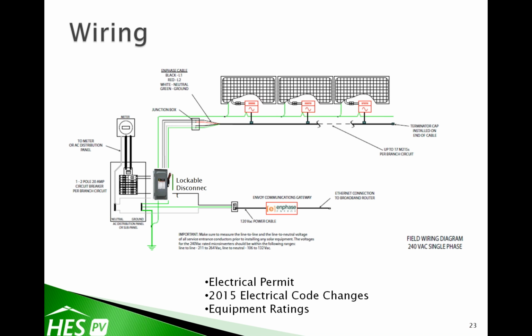Absolutely. This is one of the things that was really nice for BC Hydro to do. Probably almost 10 years ago now, we required a lockable disconnect out by the meter with a visible break. That changed, and there was a lot of cost involved, because you had to usually run wires out beside the meter, put the disconnect there—it was an expensive disconnect—and then run them back in. BC Hydro now has allowed us to just comply with the code, and the electrical code just says we have to have a lockable disconnect. It's load break rated, and there's a few other criteria there.